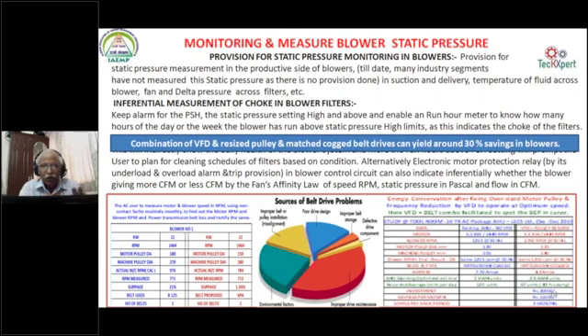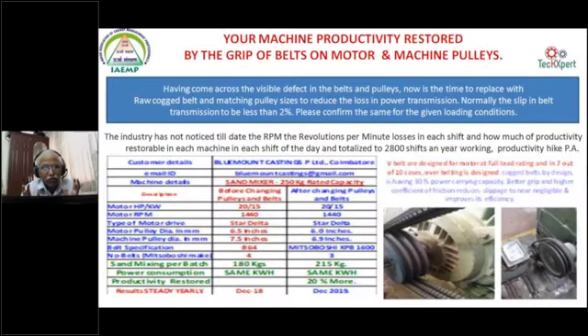You can see this was an air supply cleaner on an air conditioning plant. The slippage there was 20%, and they did not notice it. If we had an IoT based speed sensor on the motor and the machine, only 2% is allowed, and the loss of RPM is a loss to the system. This can be corrected.